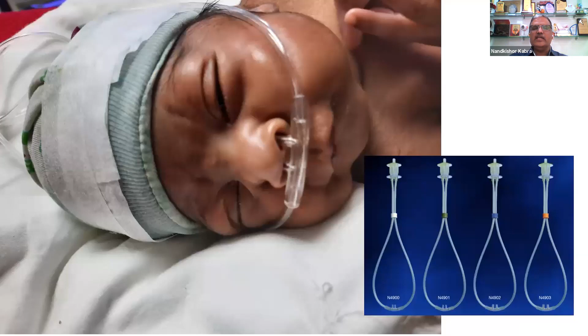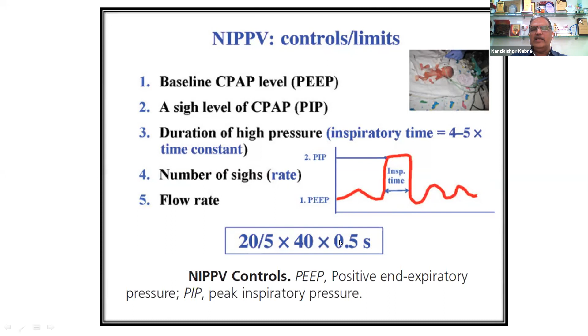And to deliver the breath, you can use any ventilator that is available which is capable of IMV or a synchronized mode. So what do you actually set? Pretty much what you set in invasive ventilation in IMV mode, you have to set here. You will set a certain PEEP, usually 5 or 6, and you would have a PIP, and generally this is 2 to 4 centimeters higher than what you would set in conventional ventilation. You would have an inspiratory time, which gives you this PIP over that period of time, and then you would have a rate, and you would have to set a flow in some ventilators. Some ventilators will adjust the flow automatically. The flow that you set in non-invasive ventilation is generally higher than in conventional ventilation because of the variable leaks that happen through the circuits. So generally when you start, you would set PIP of 20, PEEP of 5, rate of 40, I time of 0.5 seconds, and FiO2 as required.